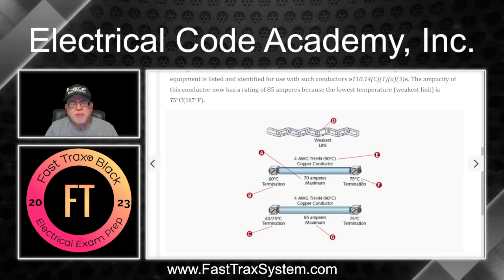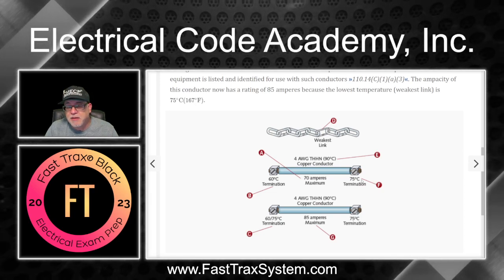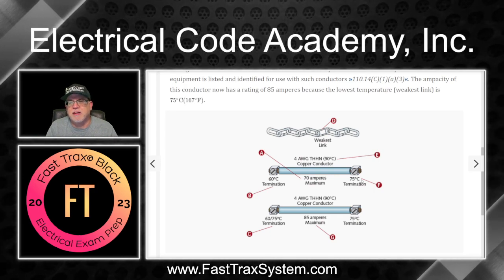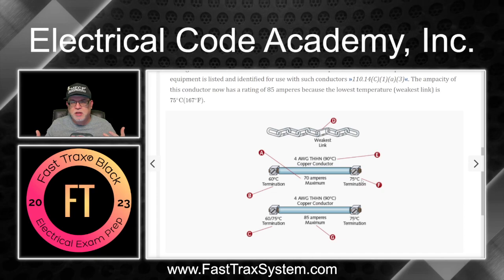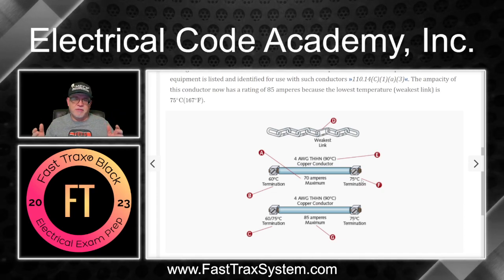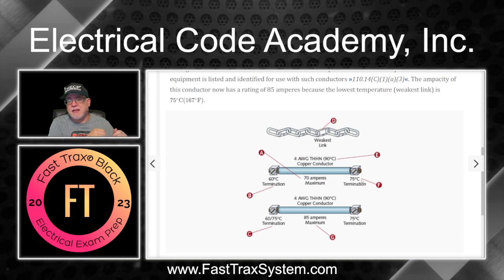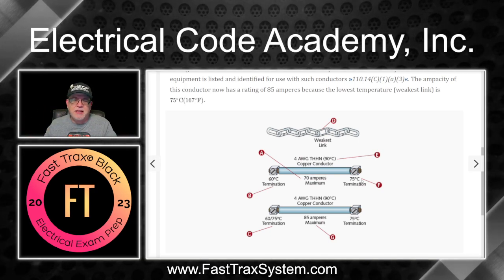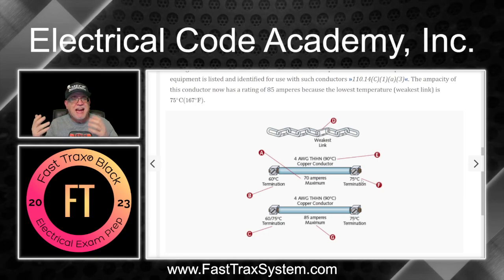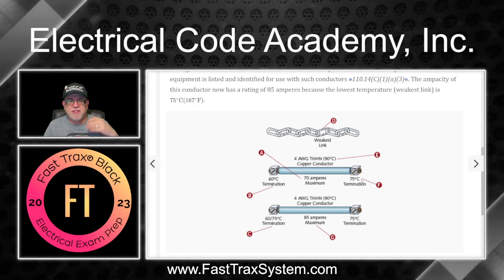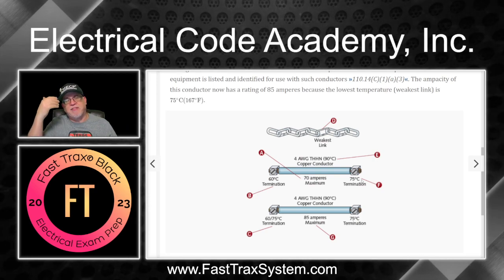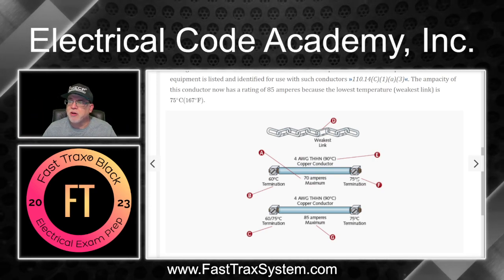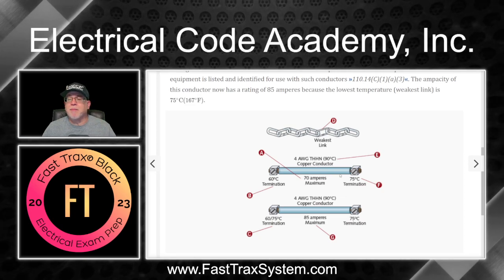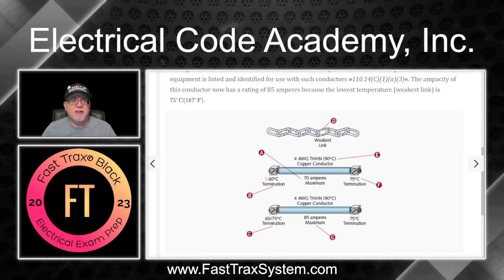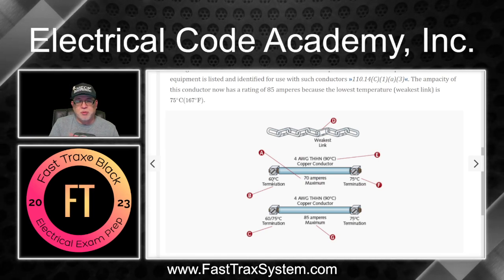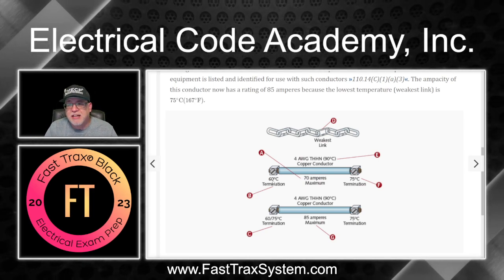Well, yeah, for adjustment and correction purposes, but you're still going to be held to the weakest link theory, and that's going to ultimately be the terminations. So remember, as I said, there's 3 elements here. There's the termination at the supply end, there's a termination at the load end, and then there's the conductor in the middle. You could have 3 different temperature ratings. You could have a 60, a 90, and a 75 at the other end. Kind of like this picture right here. And you've got to remember that the 60 right here is the weakest component, so that's going to be the limiting factor. That's what we refer to as the weakest link.